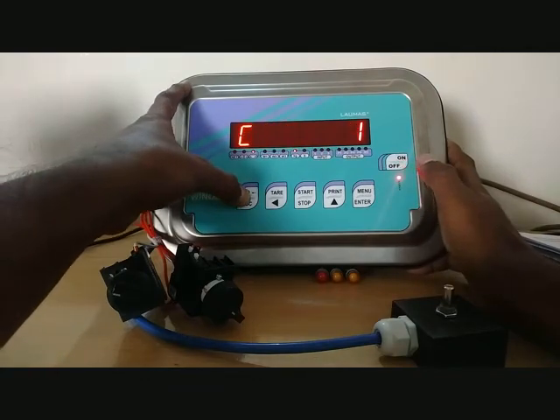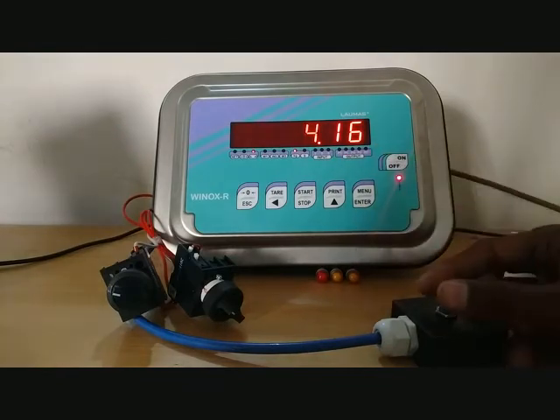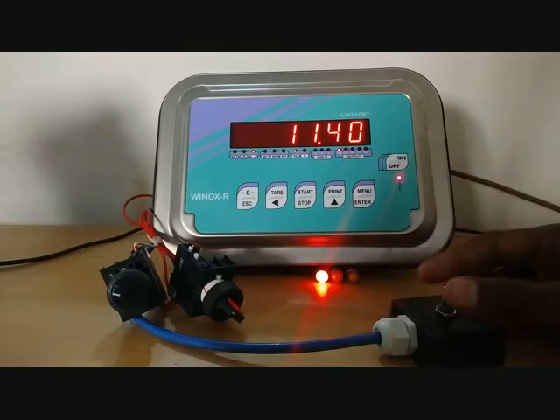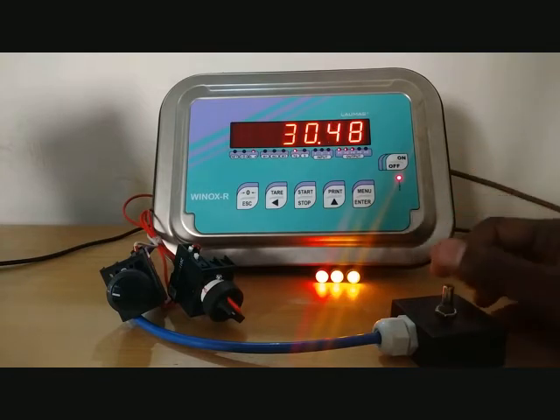We come out from the scale settings. It was at 4.16 kg, so we are simulating it up to 10 kg. Relay 1 is now on, and similarly the LED indication is also on. Now we will take it to 20 kg.